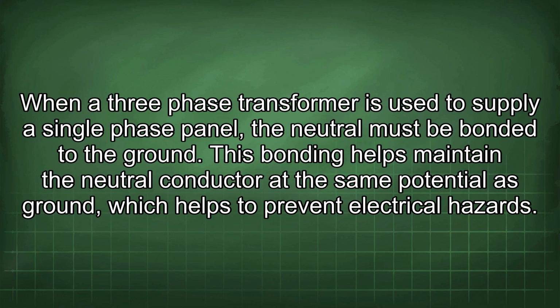When a three-phase transformer is used to supply a single-phase panel, the neutral must be bonded to the ground. This bonding helps maintain the neutral conductor at the same potential as ground, which helps to prevent electrical hazards.